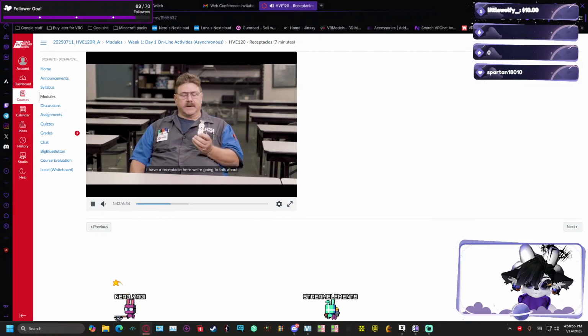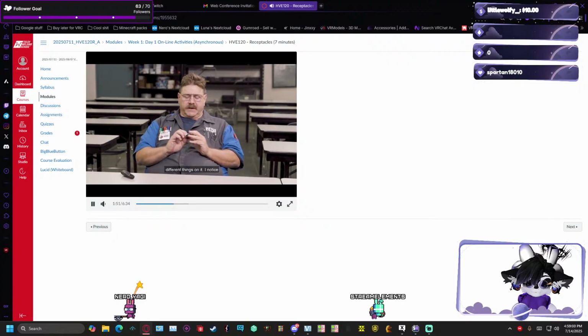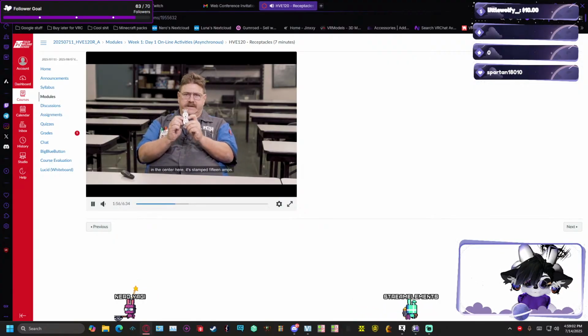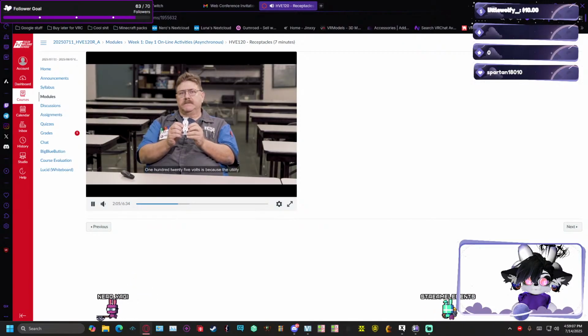I have a receptacle here we're going to talk about for a minute. This is a standard 15 amp duplex receptacle. If you look at the receptacle, there are a lot of different things on it. I noticed that in the center here, it's stamped 15 amps. That's because it's listed for a 15 amp receptacle, also for 125 volts. The 125 volts is because the utility company is allowed to provide plus or minus 10% of voltage coming to our residence, and this device has to be able to handle what the utility company might provide as far as voltage.